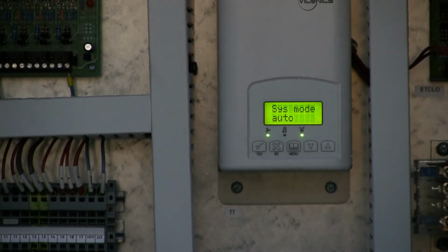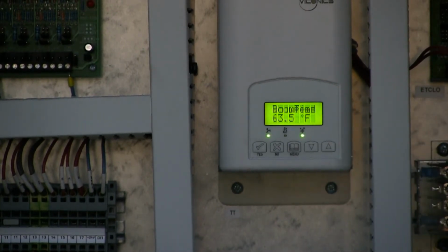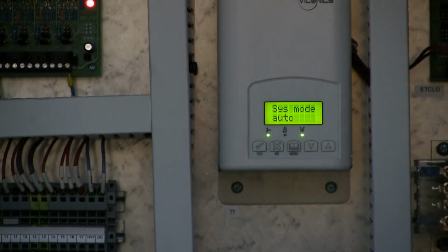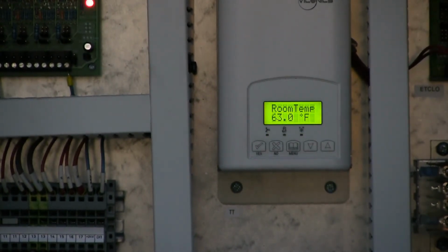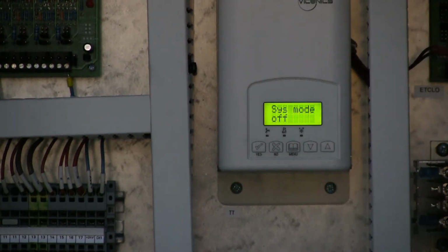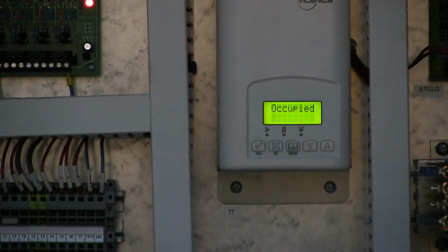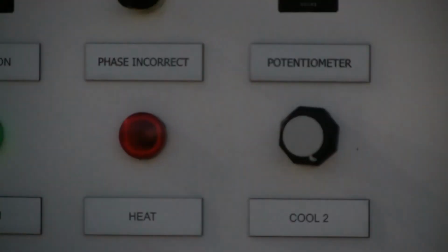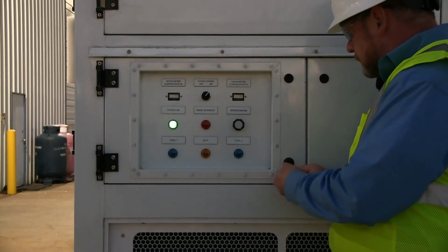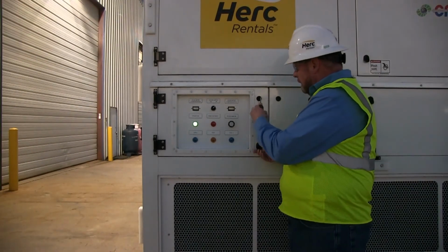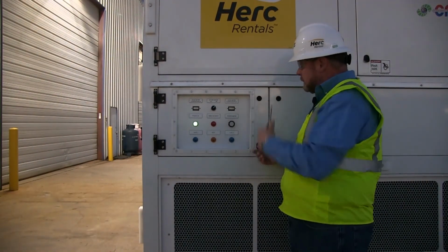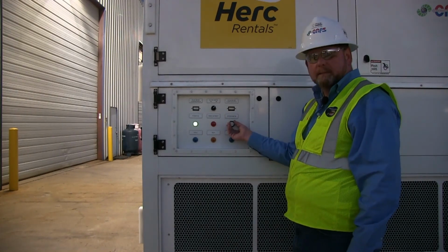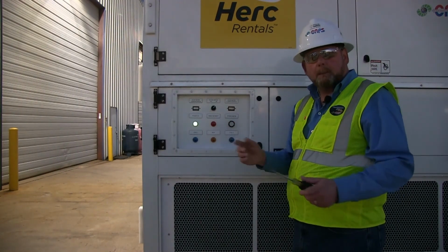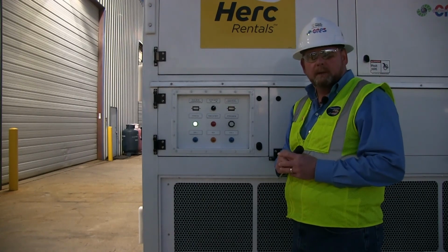The room temperature is 63.5. It's set in automatic mode, and after a period of a time delay, since the room temperature is above the cooling set point, it's going to start the cooling, which it just did. If you had set it for heating, it would simply raise the set point on in, and then the heat elements would come on. To get at any given time, you close this door back after it's been set up. Use a screwdriver to secure the front door here, and you still have the ability to adjust the airflow as needed. Fairly simple operation of the Herc 20-ton vertical HVAC unit.